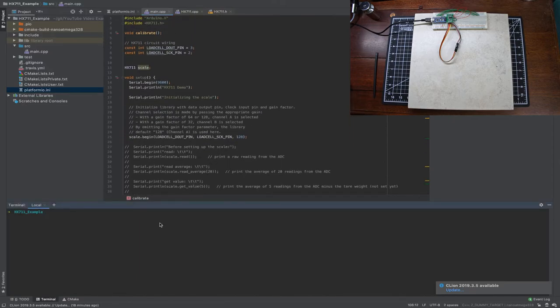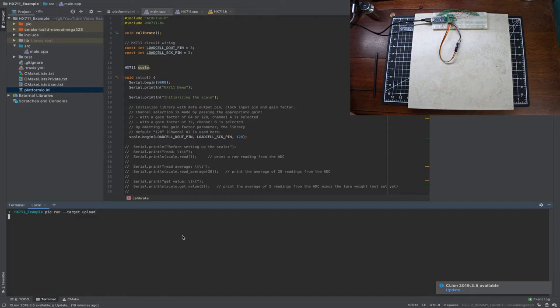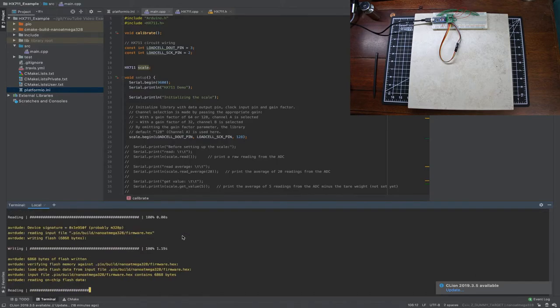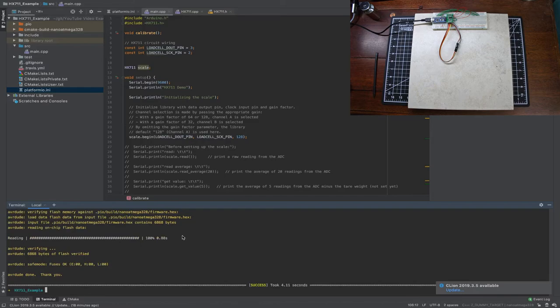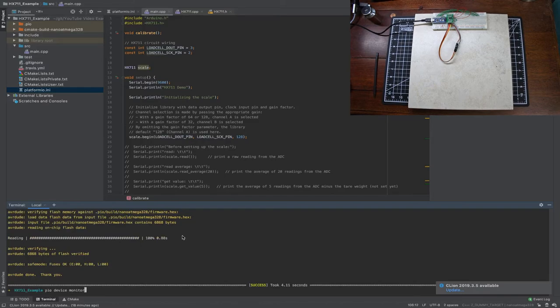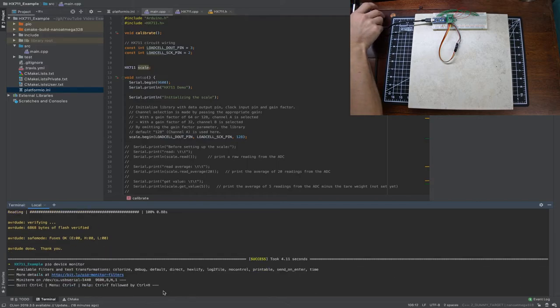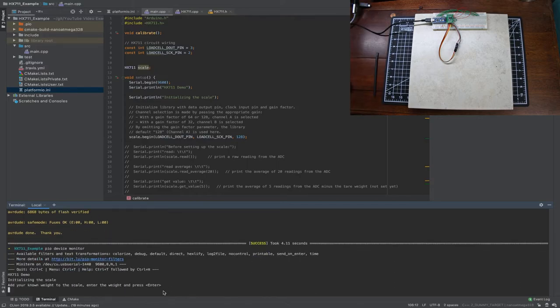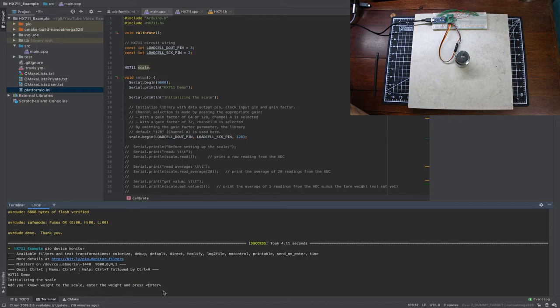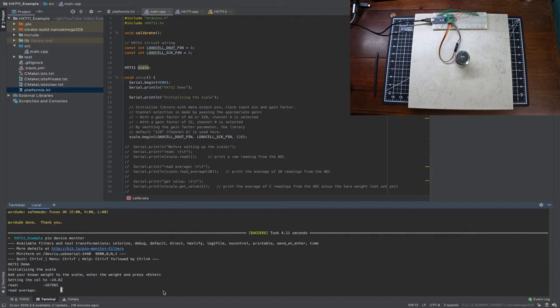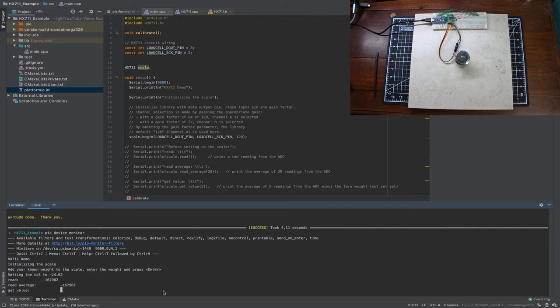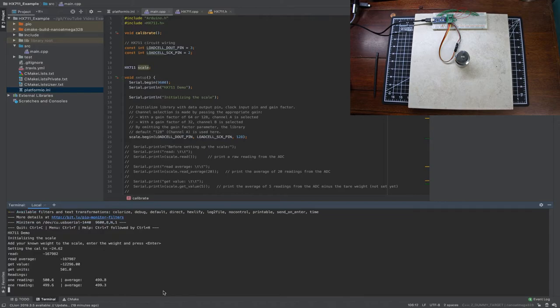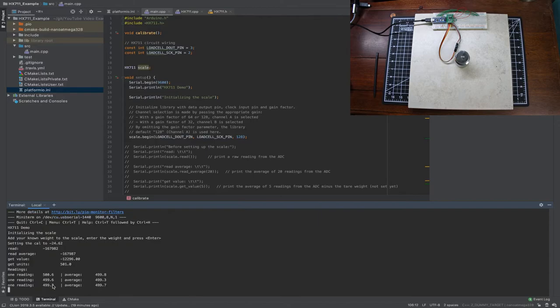All right so let me run this up and let's see. All right so I'm going to start my device monitor which is going to reset my Arduino. It's initializing the scale, okay so it's done the tare to reset everything, it's reset the calibration. Now I put my known weight on here 500 grams, I type in 500, it's not going to show you what I'm typing, it's just the way that this terminal works but I'm typing in 500 and enter.